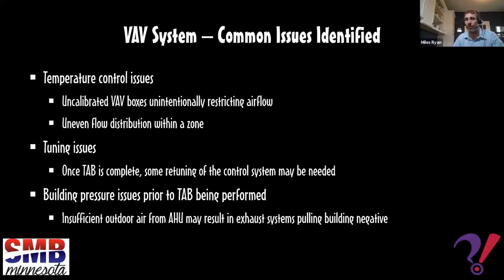They had probably roughly 30 rooftop units in this system. And those rooftop units were supposed to provide the fresh air to the space. So even when it's really cold out, and in some of our testing it was negative 10 degrees out there, you'd still want to be bringing in a minimum amount of outdoor air to meet the ventilation requirements of the space, as well as to meet the makeup air requirements for any exhaust systems. Well, all of these rooftop units had their dampers set to 0% open during these very cold times. So we were not bringing in any cold outdoor air into the space, but all of the auxiliary exhaust systems were operating. So the building was being pulled excessively negative. So that resulted in a lot of unconditioned humid air in the summer being brought in, and it also resulted in very cold drafts being brought in the winter.